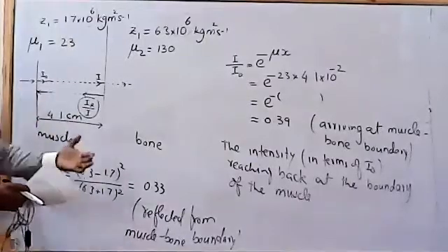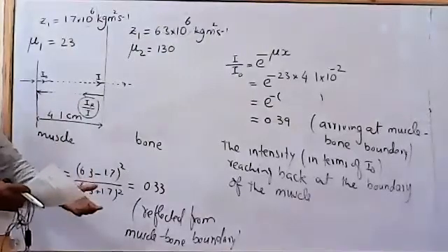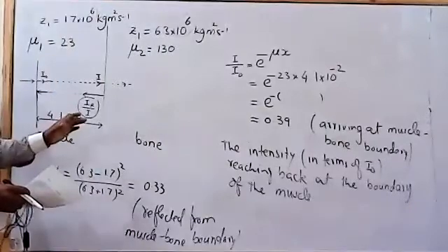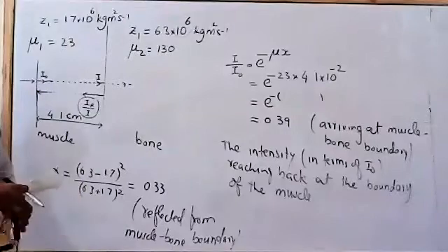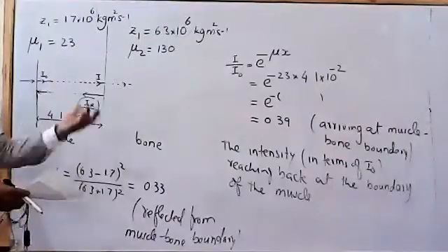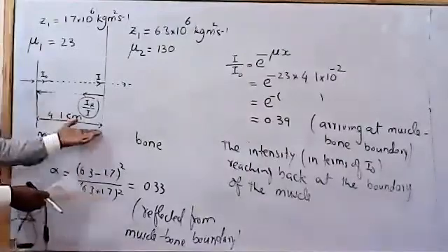The transducer makes use of it and converts it back into the voltage pulses, and then this information is given to the sensors, and they make use of this information to make that image that we see on the screen. So what percentage is arriving here is important calculation, because we want to know at least what strength we have coming back.